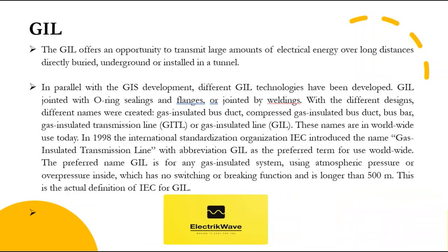The GIL offers an opportunity to transmit large amounts of electrical energy over long distances, directly buried, underground, or installed in a tunnel. Different GIL technologies have been developed, including GIL jointed with ring sealings and flanges, or jointed by welding. With the different designs, different names were created: gas insulated bus duct, compressed gas insulated bus duct, bus bar, gas insulated transmission line (GITL), or gas insulated line (GIL). In 1998 the International Standardization Organization IEC introduced the name 'gas insulated transmission line' with abbreviation GIL as the preferred term for worldwide use. The preferred name GIL applies to any gas insulated system using atmospheric pressure or overpressure inside, which has no switching or breaking function and is longer than 500 meters. This is the actual IEC definition of GIL.